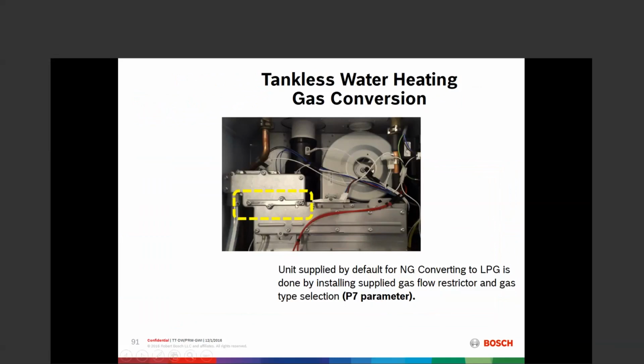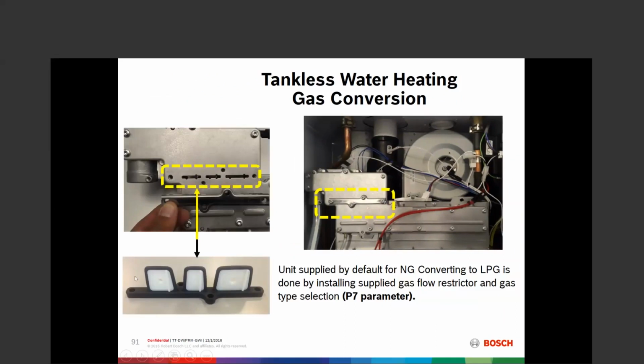Fan this cap here to the left of it, 1, 2, 3, 4, number 25 screws. 4 screws come off, the cap comes off, behind there's a gasket. We no longer need the gasket. The gasket gets replaced by a gasket that has these brackets, and these brackets accept the orifices for the LP conversion. They are shipped separately in a separate bag.